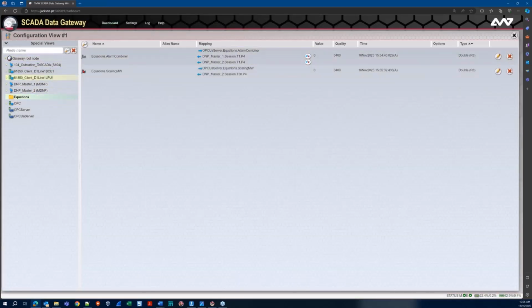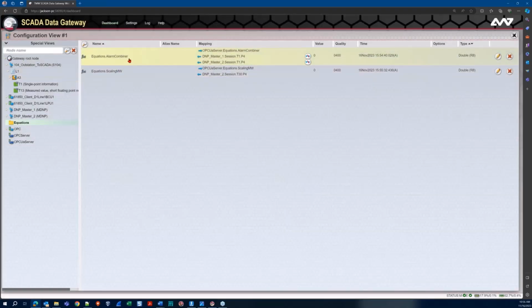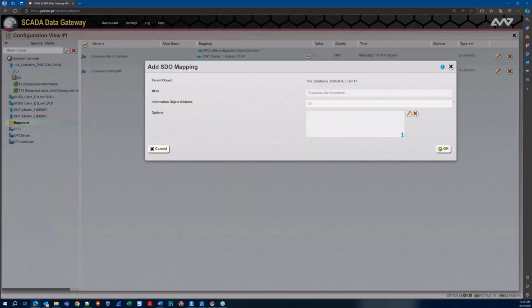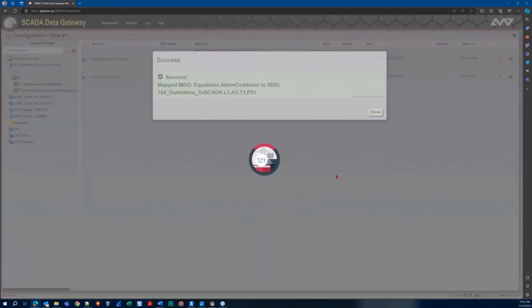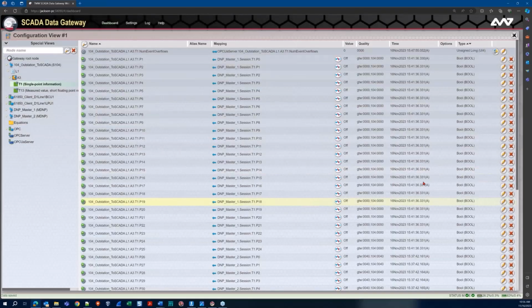Now, if I want to take one of these and map it up to my 104 outstation, I easily can. So that alarm combiner we talked about before, just take it and drag it to T1. Next available point is going to be 51, so just hit OK, and we are good to go there.